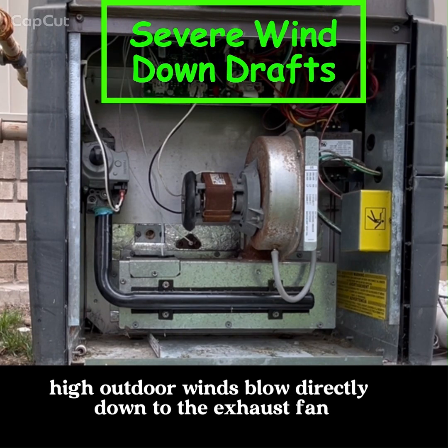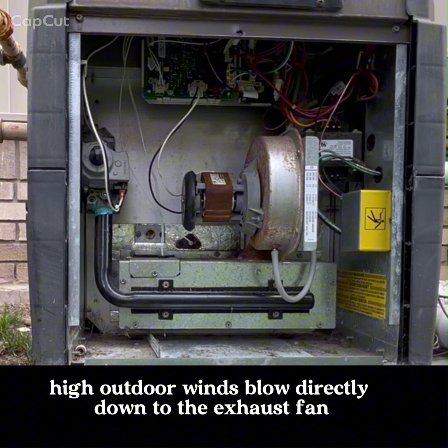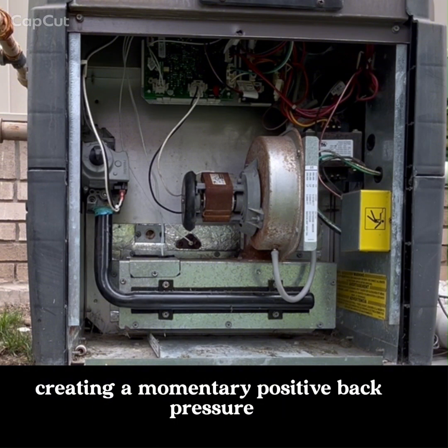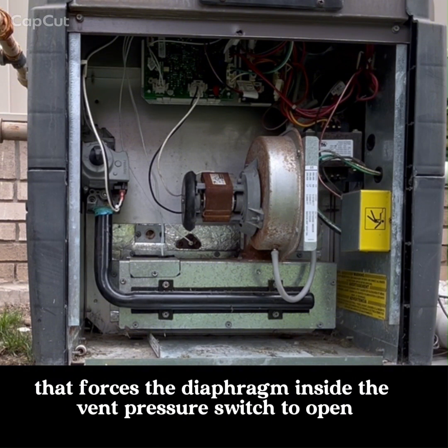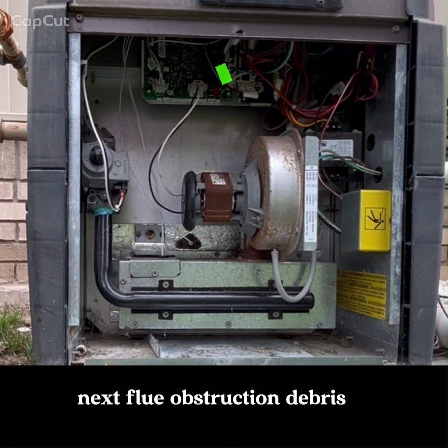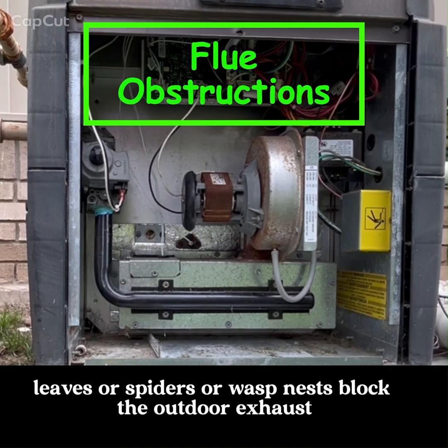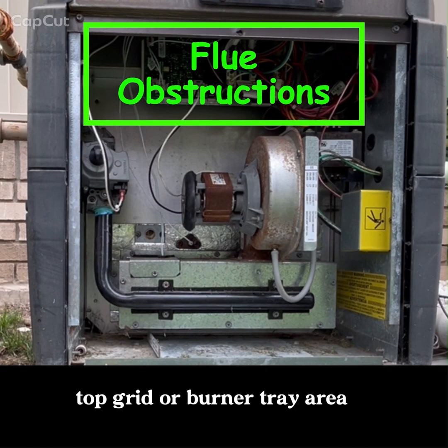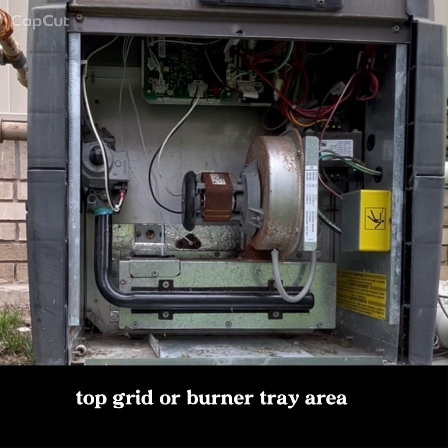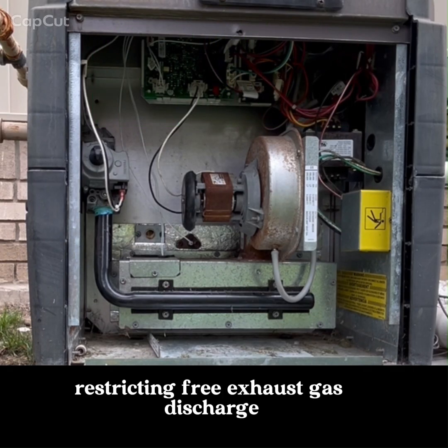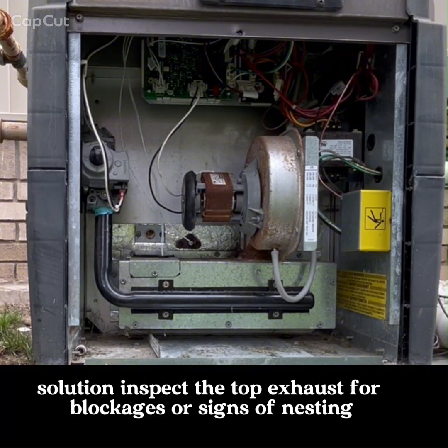High outdoor winds blow directly down to the exhaust fan, creating a momentarily positive back pressure that forces the diaphragm inside the vent pressure switch to open. Next, flue obstruction. Debris, leaves, or spiders' or wasps' nests block the outdoor exhaust top grid or burner tray area, restricting free exhaust gas discharge. Solution: inspect the top exhaust for blockages or signs of nesting.